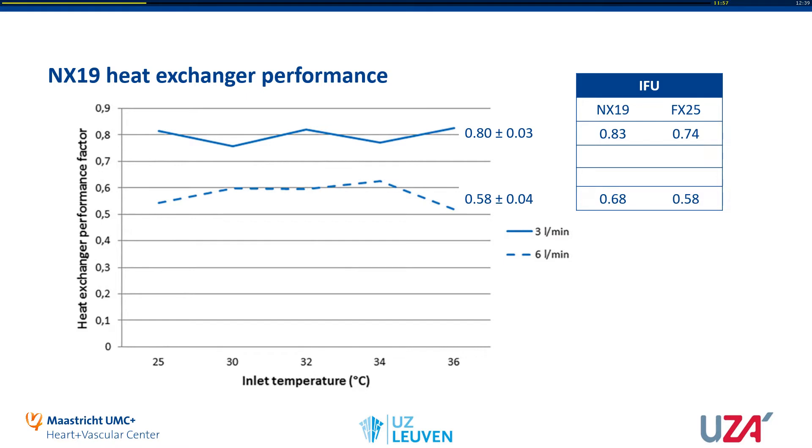These are the results from our heat exchanger performance tests. We made an experimental setup with one NX19. We measured at two different flows: three liters per minute, which is the solid blue line on top, and six liters per minute, which is the dotted line. We gave five different venous temperatures into the NX19, ranging from 25 to 36 degrees. We then started the heater-cooler unit attached to the NX19 and measured the heat exchanger performance factor. At three liters per minute, the performance factor was 0.8, and at six liters per minute it was 0.58. According to the instructions for use, the performance factor should be 0.83 at three liters per minute — quite comparable to what we found.